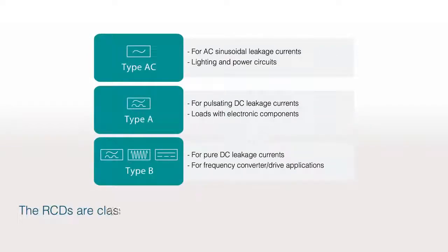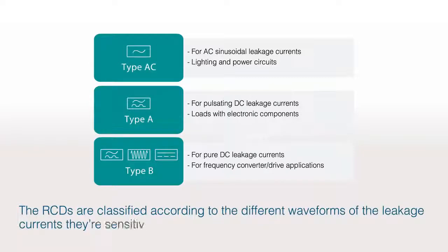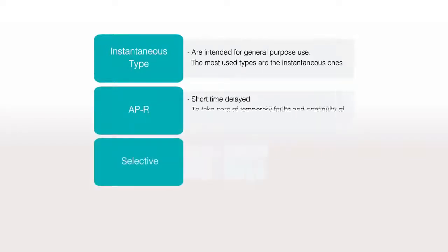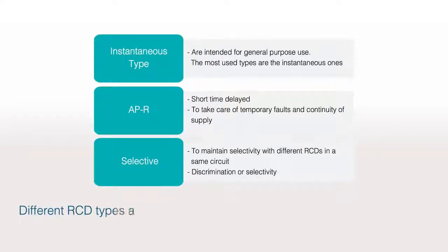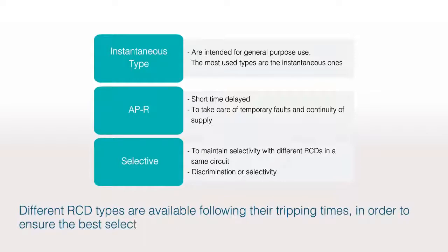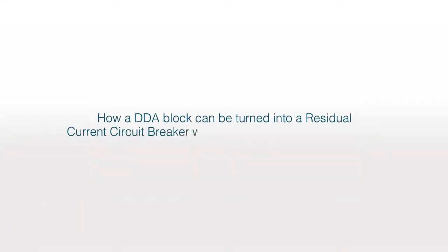The RCDs are classified according to the different waveforms of the leakage currents they're sensitive to. Different RCD types are available following their tripping times in order to ensure the best selectivity with other RCDs installed in the system. How a DDA block can be turned into a residual current circuit breaker with overcurrent protection, RCBO.